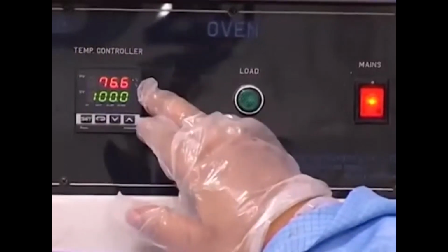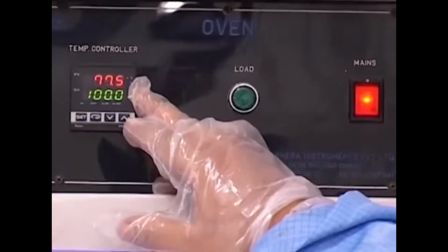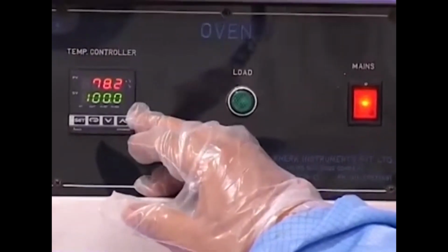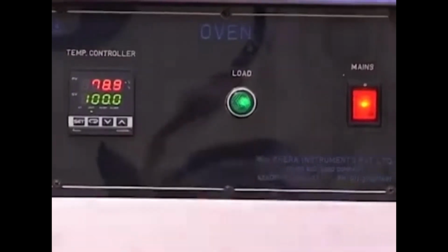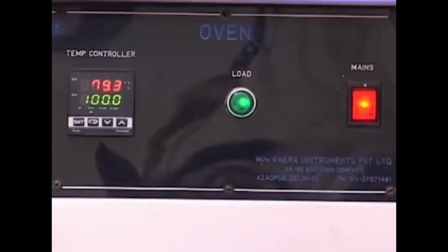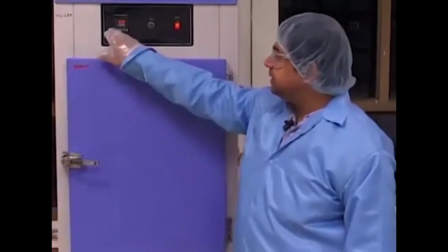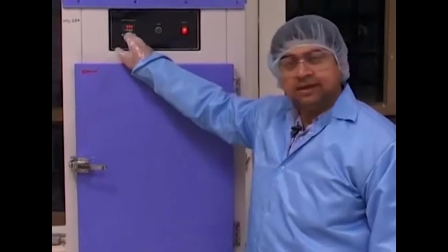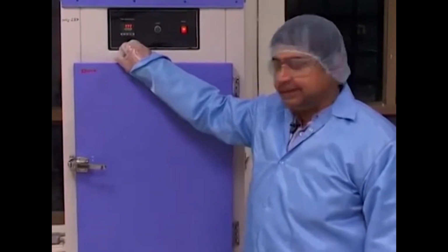100 degrees. So this temperature, which is also the proportional integral differential temperature, slowly equalizes to this set value after a while, and there is some kind of flickering around the set value. It does that flickering and slowly attains the set value point. So now, as you are seeing here, the variable value has almost reached 100 degrees, and this is time enough for our wafer to get loaded inside and get dehydrated.